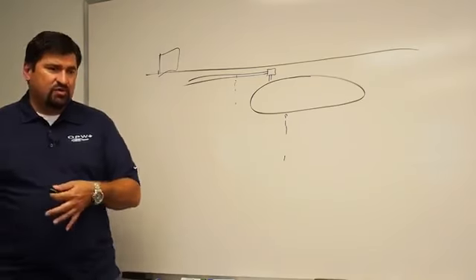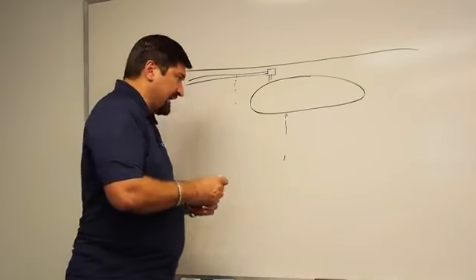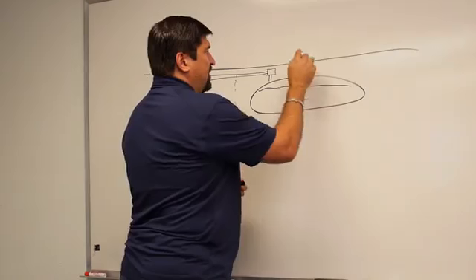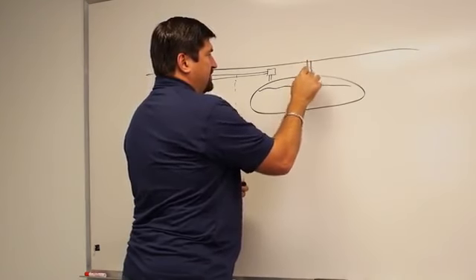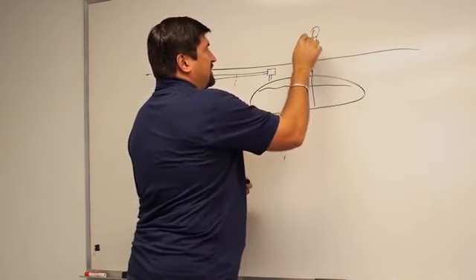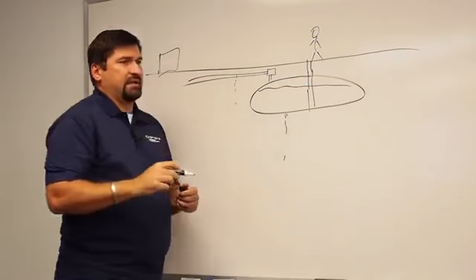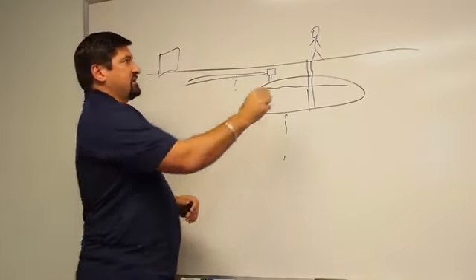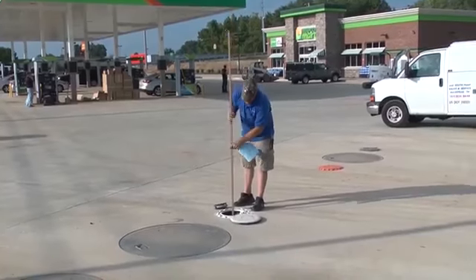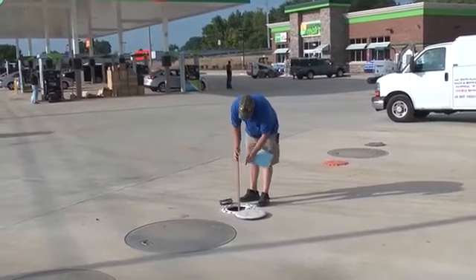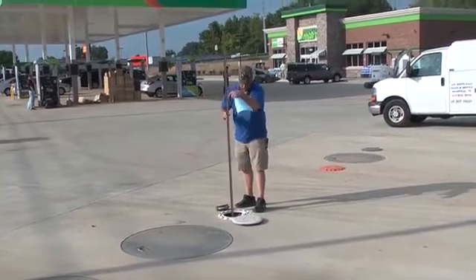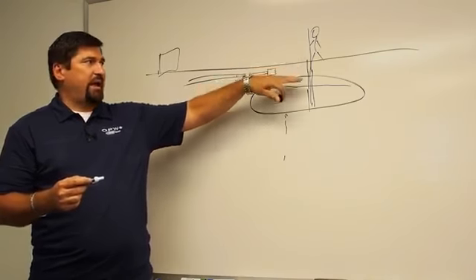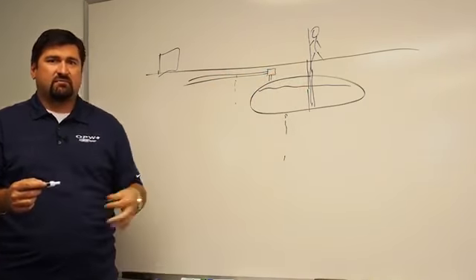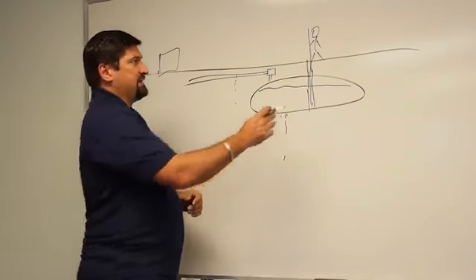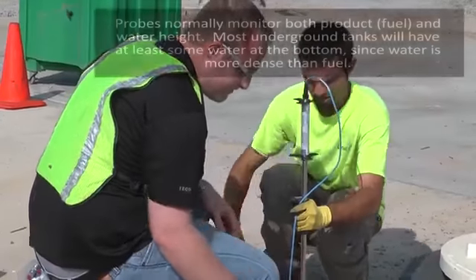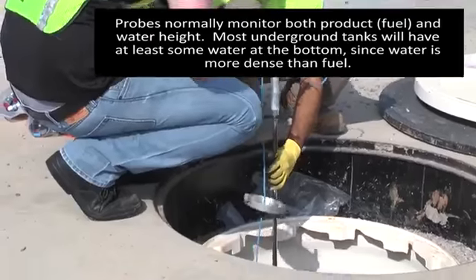But the other reason why most people will use a tank gauge is because they need to know what the level is when the person up on the ground can't see what's in the tank. So what he wants to do is he's going to take his stick, he's going to drop it in here, he's going to read that stick to see what the product level is. Well, when you look at this, it's costing you money because you're paying somebody to go out and do this as a manual process.